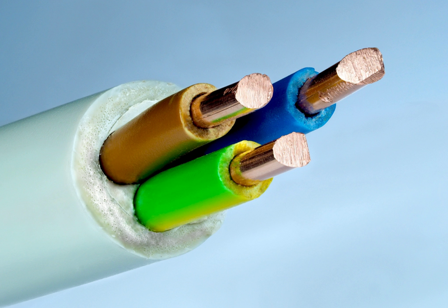Inorganic coatings and boxes around cables safeguard the adjacent areas from the fire threat associated with unprotected cable jacketing. However, this fire protection also traps heat generated from conductor losses, so the protection must be thin. To provide fire protection to a cable, the insulation is treated with fire retardant materials, or non-combustible mineral insulation as used in MICC cables.